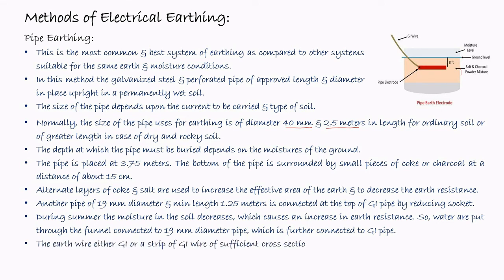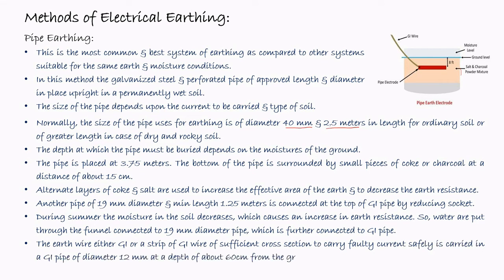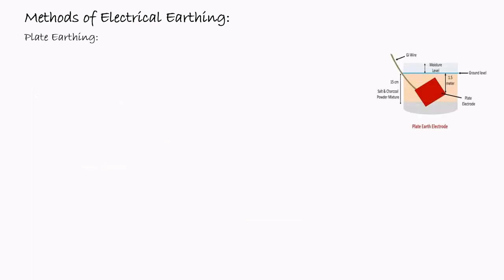The earth wire, either GI or strip of GI wire, is of sufficient cross section to carry the faulty current safely. It is carried in a GI pipe of diameter 12 at a depth of about 60 centimeter from the ground. So this is the concept of the pipe earthing. Next is the plate earthing.